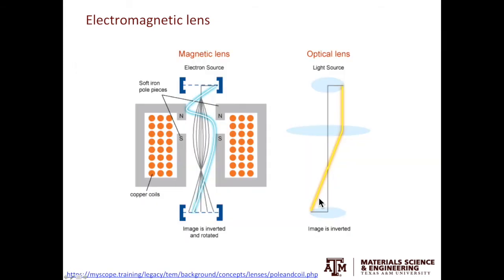There is one thing you need to know regarding the electron path inside TEM as well as in SEM. The electron beam does not go straight down from the electron source through the column. It actually rotates, it goes in a spiral. The result is that when we change the magnification inside TEM, the image actually rotates. This is because we are capturing different parts of the spiral as we change the magnification. There is a special term to describe this phenomenon called the magnetic rotation.